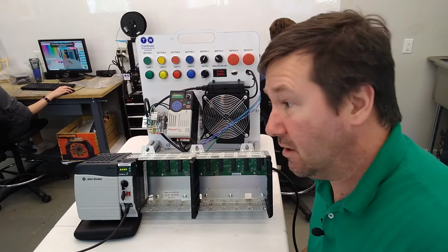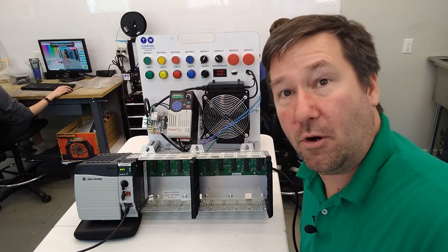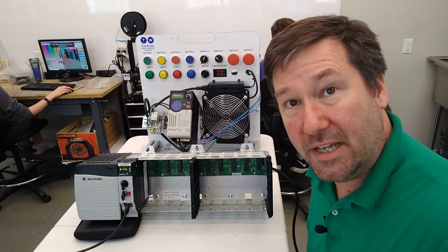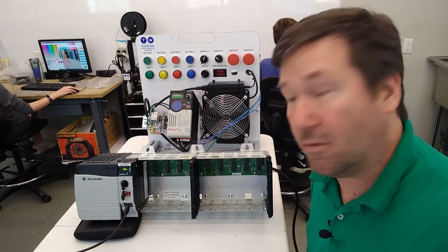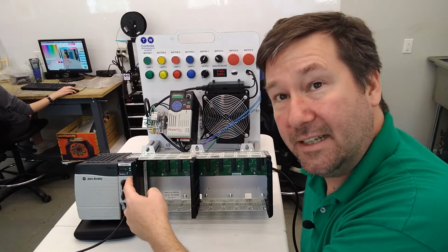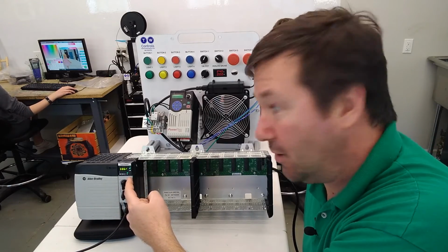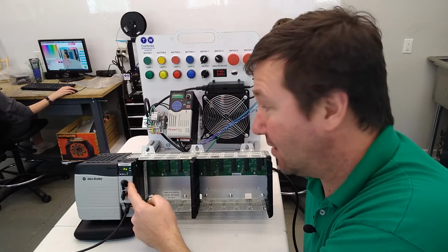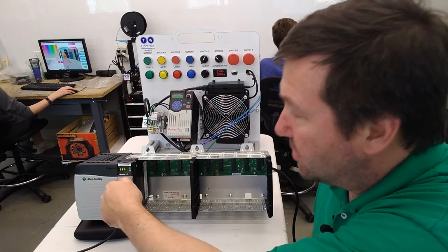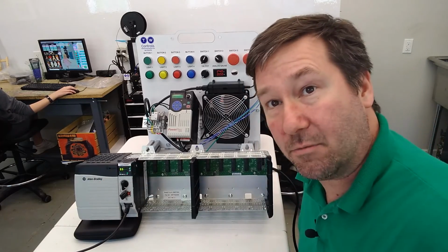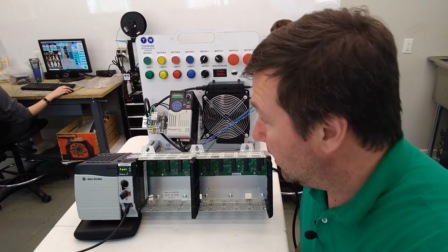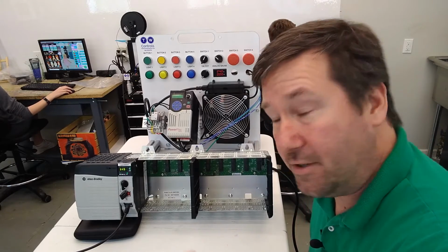Meanwhile, somebody has found out, hey, I found the broken switch, and they replace the switch and the machine still won't run. That's because the PLC is now in program mode. I can't tell you the times I've actually had to go on a job site and reach over here, switch it to run and switch it back to remote and walk off. So let's go through that. Make sure you understand that.